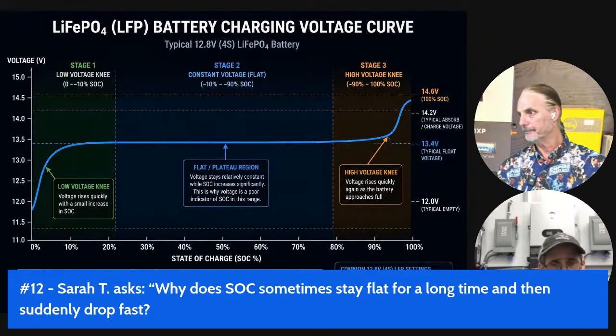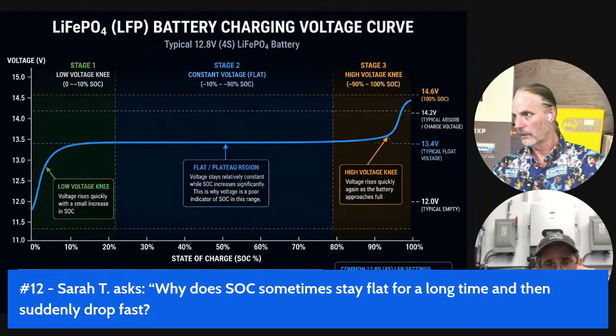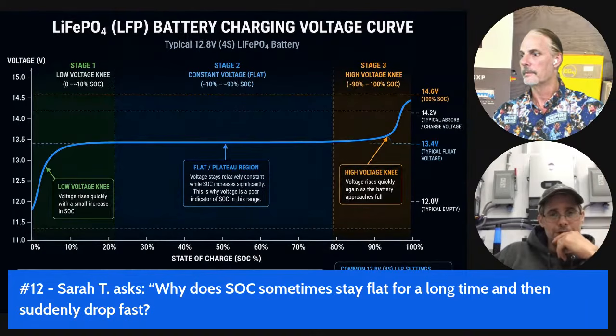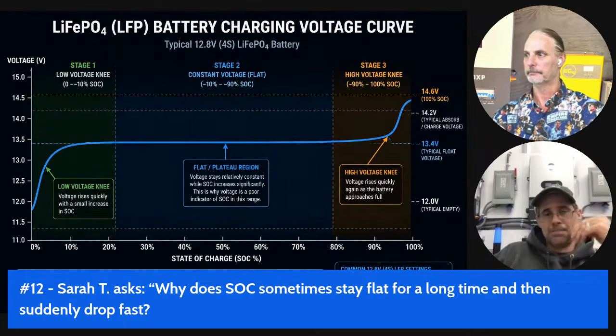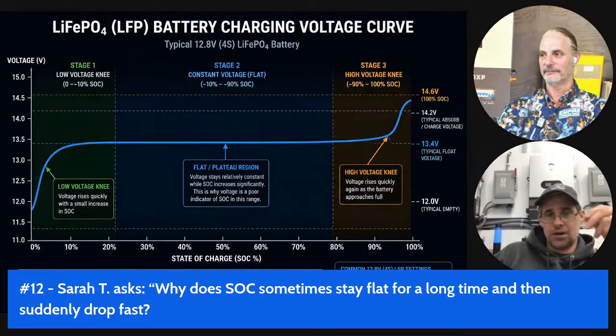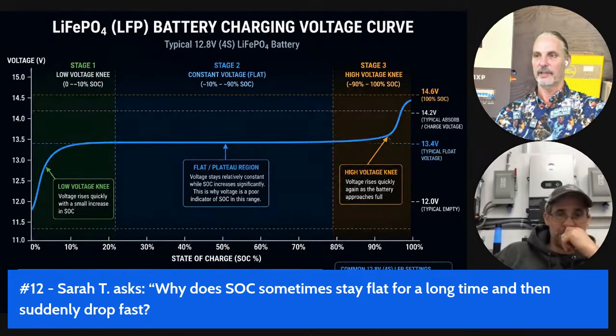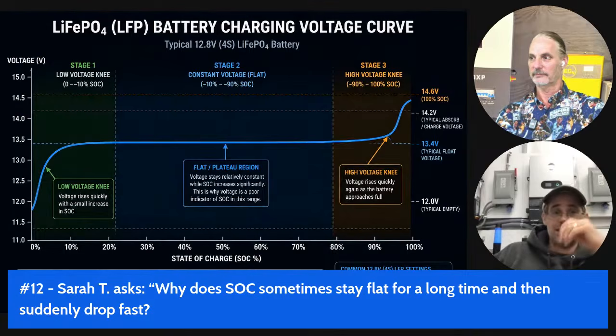You got anything to add, Mike? Yeah, the other thing is if SOC stays flat and then suddenly drops off, and you notice it's at the very top, maybe some of your batteries aren't fully charging to 100%. It says it's 100%, but the cells aren't balanced - it believes it's at 100% because the BMS kicked off when one cell was a runner and hit high voltage before the rest, cutting off the charge when the battery was truly at 80%. That one runner cell made the BMS think it was 100%. If the cells or batteries aren't balanced to each other, it can drop in those scenarios.